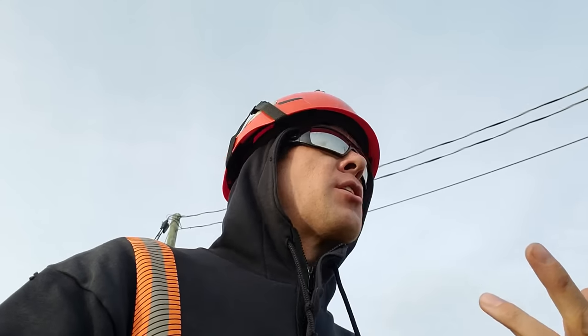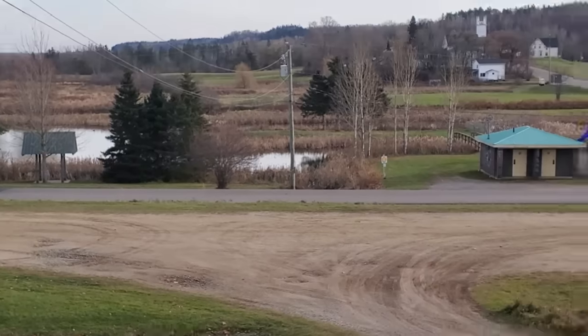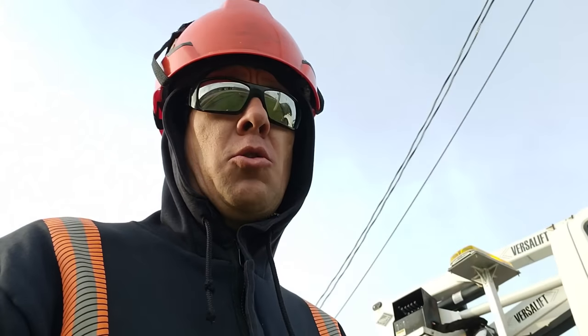Before taking the stick out and checking that, I did want to make sure the main line was out. There are several other customers off the main line so it wasn't likely. I can see the cutout feeding the sideline way over there on that streetlight pole — it was closed. We went down to a few of these shops and checked the meters: power's on, and even down the road power's on in that building. So at that point I started scratching my head. We grabbed the tele-stick, opened that cutout door, brought it down to the ground — fuse was intact, even popped it out, did a continuity check, make sure the fuse link wasn't blown inside. It's good.